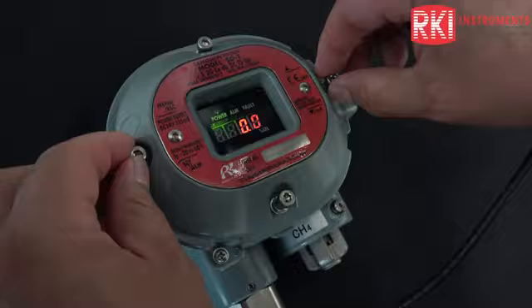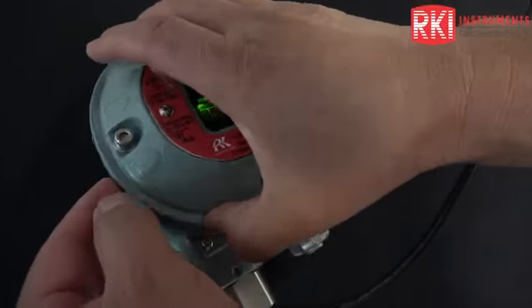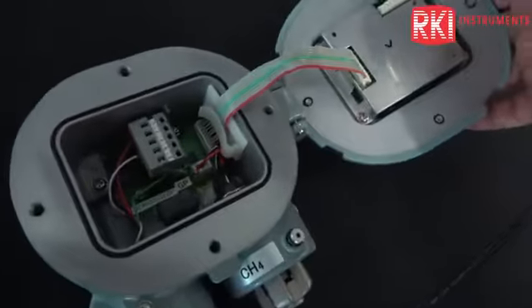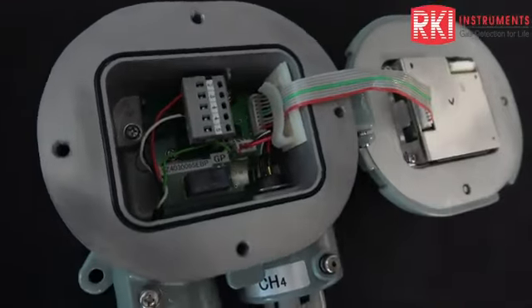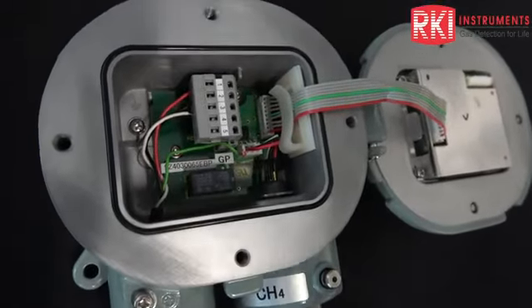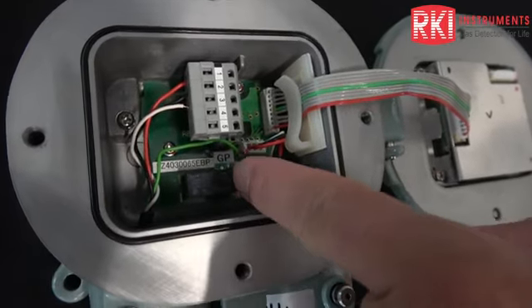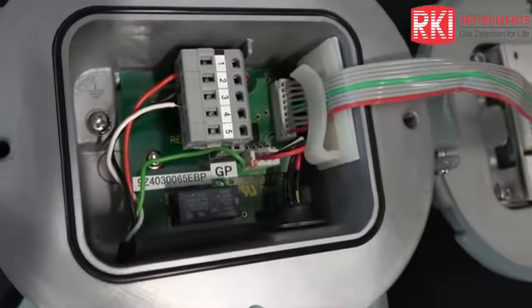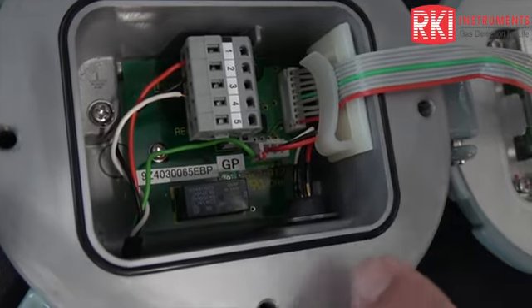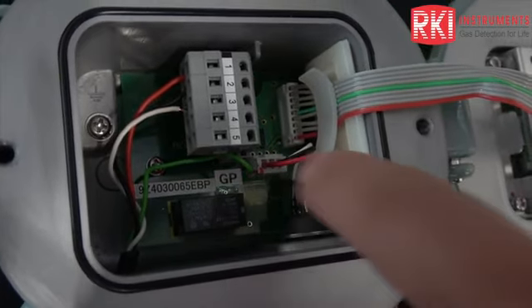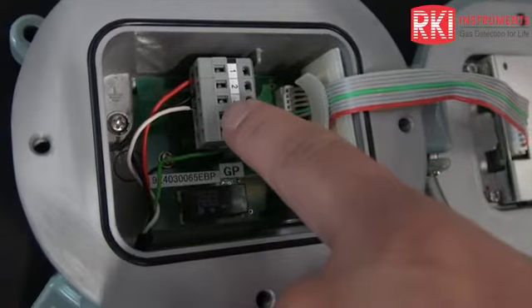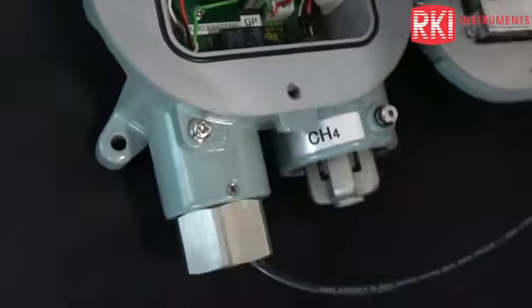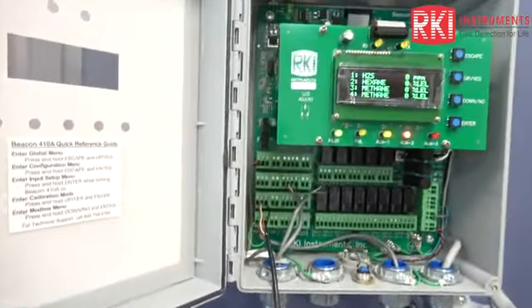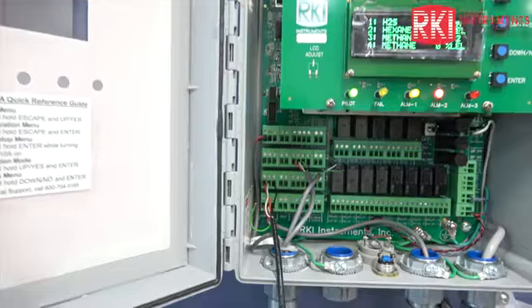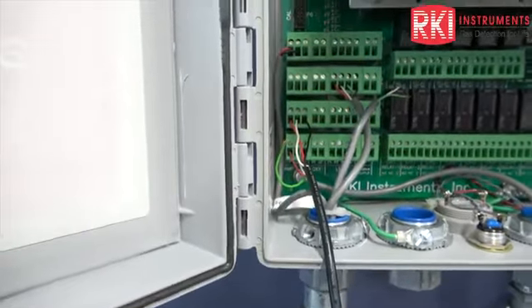So I've already pre-loosened these screws here, and then I'm just going to open this up to show you the inside. Basically, it's just a simple PCB board in the back. You've got a relay here, and then your terminal connector here. So you've got the sensor wiring going from right here, this harness, to that connector, and then from the connector down out of the hub, and then up to a controller that you might be connected to. In this case, we have it connected to our Beacon 410A 4-channel controller.